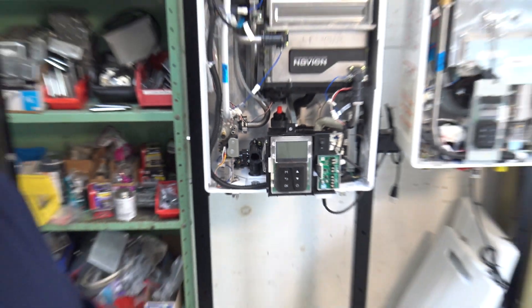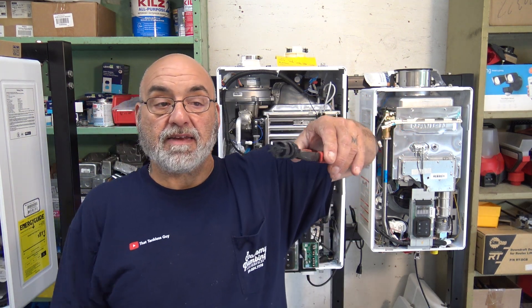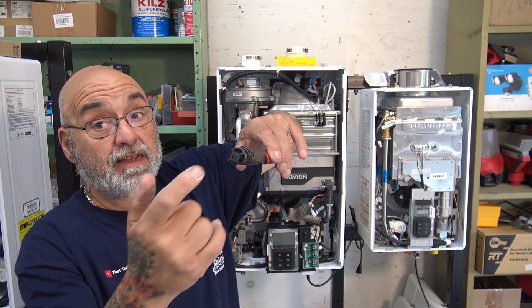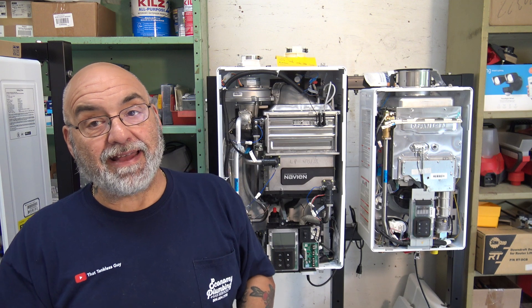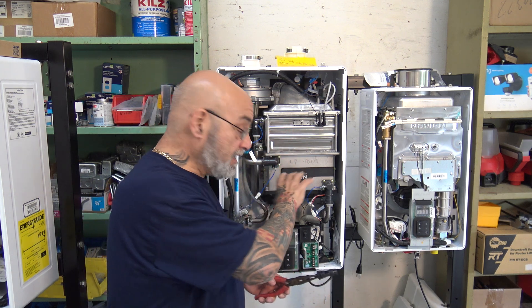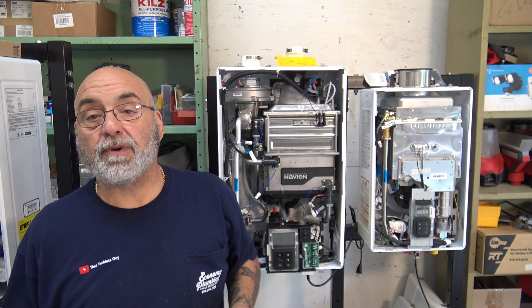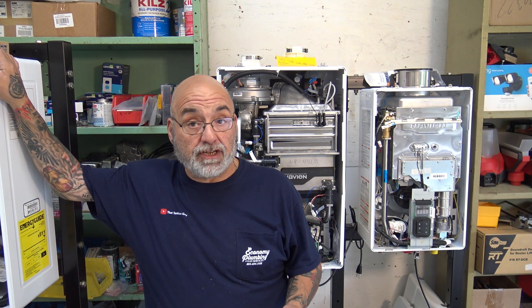Here's your check valve. There's a spring with a little plunger — you can see if it's operating correctly. It should spring back in. There is a way for an emergency fix if you have the parts box. Parts boxes are available for the NPE and the NCB — heat exchanger, pump, tank come separately — but everything else inside comes in the black box. Inside the parts box is a bag that has a new check valve.